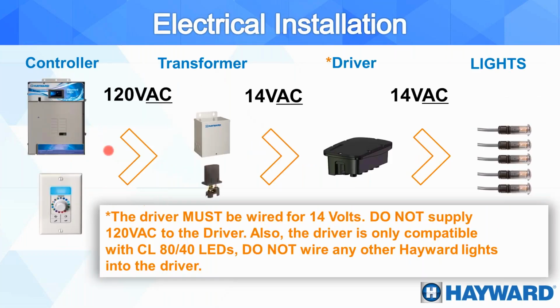So here we see it another way. We feed from the high voltage line to the transformer. So this is obviously high voltage again. From the transformer, we go low voltage, 14 volts once again, into our driver. And from the driver, we come out once again with 14 volts into the lights. Remember that each driver is able to support up to 5 lights. So keep that in mind.